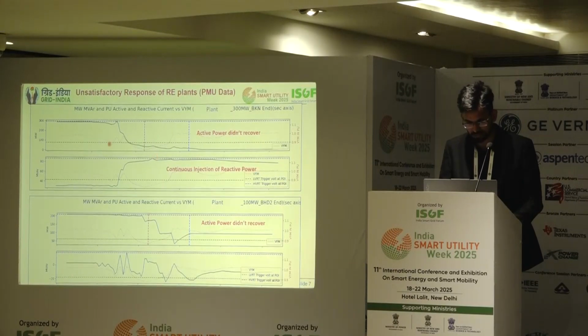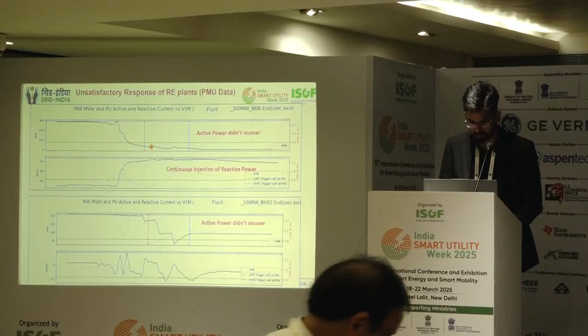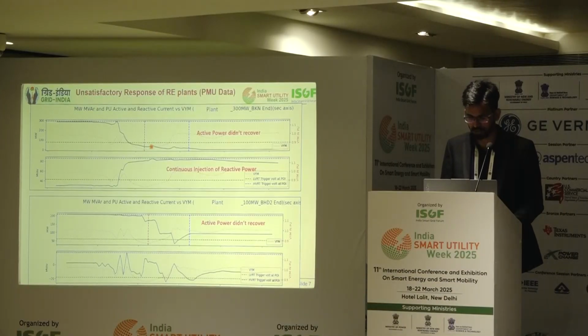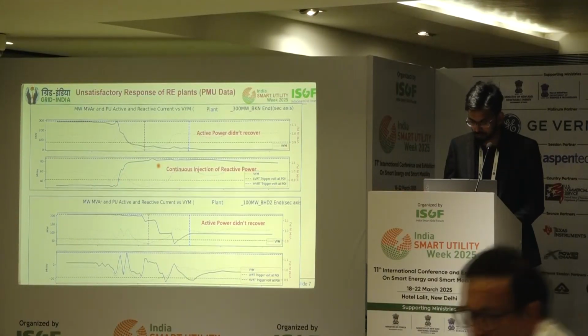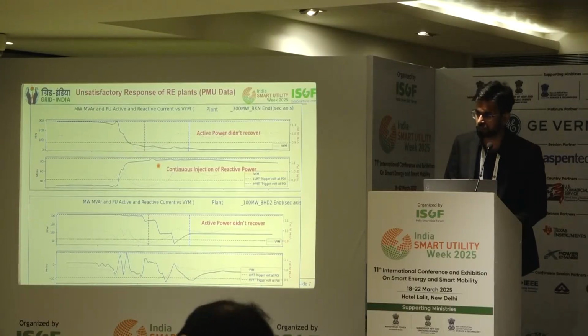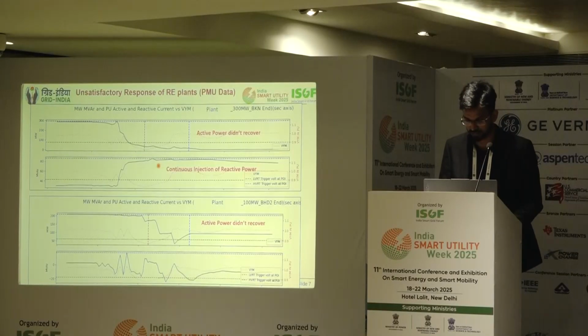In this picture, we observe the plant connected at Bikaner. When the voltage reduced below its LVRT trigger point, this dotted line, we observed the generation started declining and the whole plant disconnected from the system. This is totally different behavior of the plant from what is required as per the standards. Also, in the second plot, we can see the MVAR injection of the plant. It continuously injected reactive power into the system, which caused overvoltage in the system and tripped many 400 kV and above lines during this event.